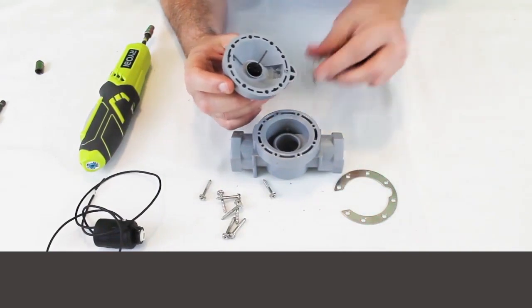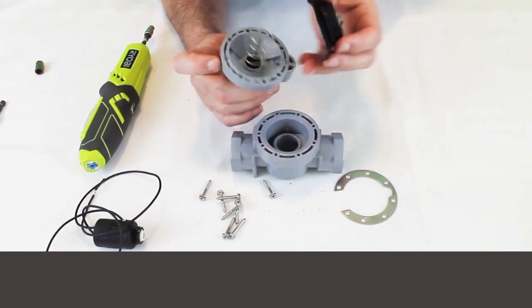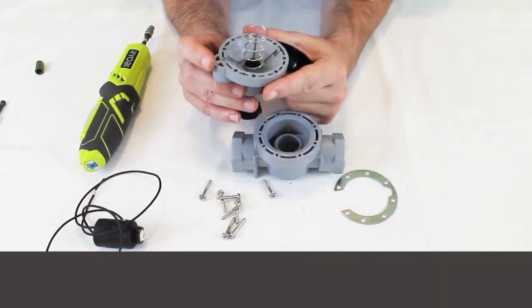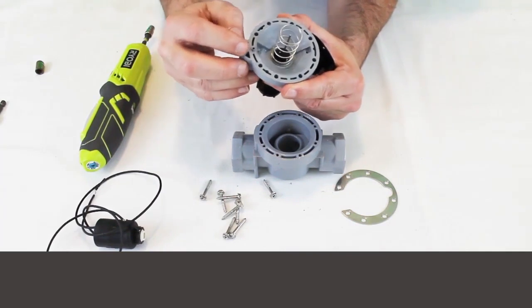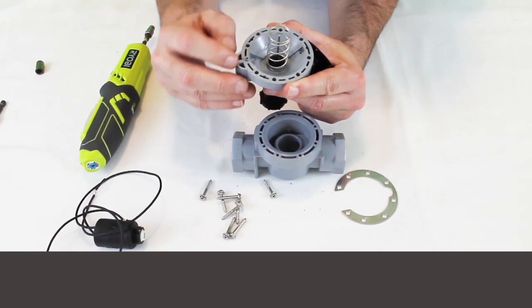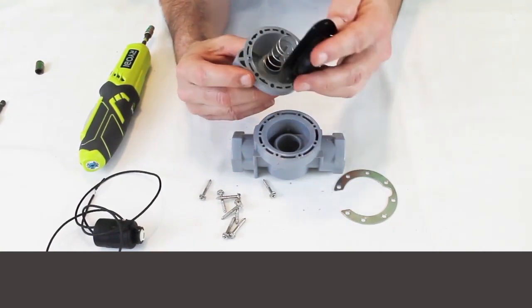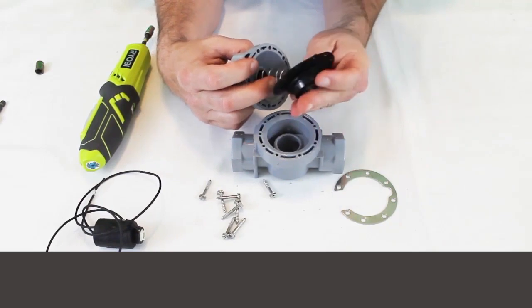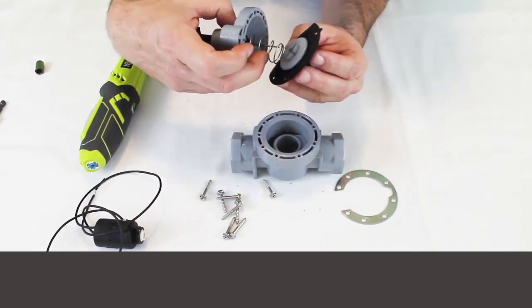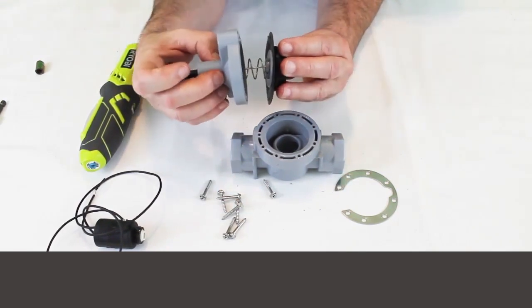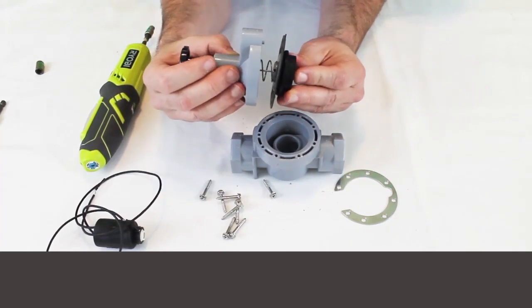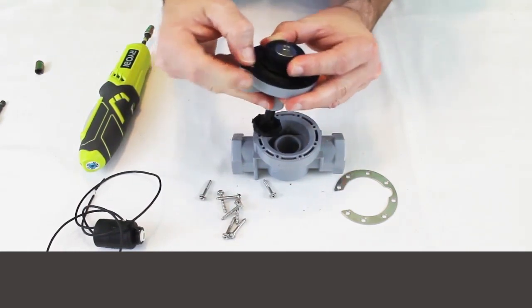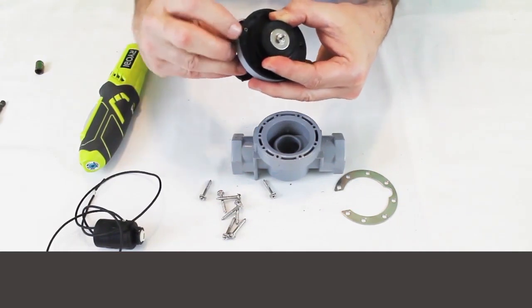We're going to put our spring back on here. We're going to spin this around, check our little piece right here. This little piece right here for the solenoid pilot hole is raised. So the spring moves around a little bit and it seats right on top of here, plus the pilot hole. Make sure that your spring is in the proper place, get that pin in that hole, and then spin it around and get it to where you can push the hole in the diaphragm down on the little nub there.